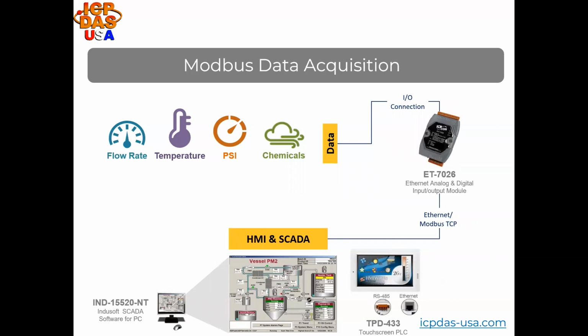Data acquisition is the process of sampling physical information and the conversion of the collected information into digital values for programs to use. Data acquisition information is used for implementing control logic operations based on conditions like the turning on of a fan based on the temperature, the turning on of a pump based on tank level, and the opening of valves based on pressure levels.